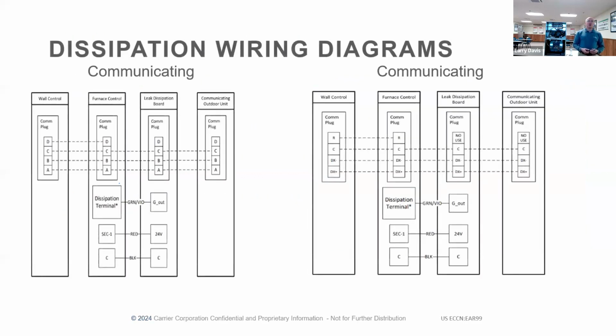So looking at a little bit of the wiring here, and you're going to see this a lot this morning. You have a wall control where you have the 4 communication wires running to it, and the ABCD or RC, DX minus, DX plus, depending on what you're dealing with. That goes from the furnace control to the dissipation board where you're only wiring A, B, and C. And then you see it goes from there to the outdoor unit. Just a daisy chain or zone board, all that fits in the same daisy chain. And the C going outdoor, that depends on, again, the unit you're using.